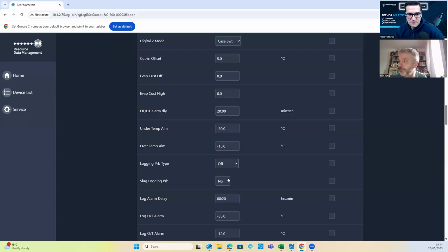Yep. A logging probe is something that a few manufacturers do. RDM's had it for years. You can fit what they charmingly call a slugged probe. Everyone loves a slug in their cabinet, which is a probe stuck in a big block of polystyrene that goes under a shelf. It responds much more slowly, as it was originally designed, like a chicken would if it was on a shelf. Because just because the air temp's gone to 10 degrees, if it's a chicken and it was at 2 degrees 5 minutes before, it ain't going to be 10 degrees in 5 minutes. So that gives you a much more stabilized response for the shelf temperature.